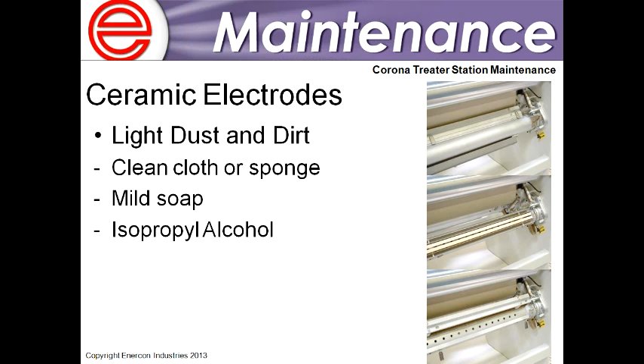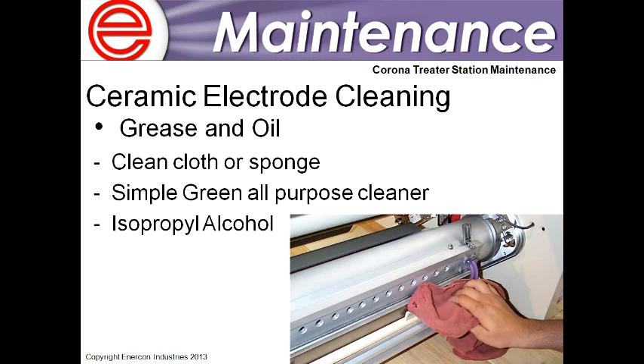You also want to make sure, to Matt's point earlier about surface prep, and I've seen this quite a bit over the years, people will take an alcohol and a cloth and wipe the surface of the electrode down, but they will not remember, or some don't even realize, that the electrode assembly has hinge features that let them access the back of the assembly. So it's really important that when you are taking the time to do this quick maintenance step, you open the electrode assembly and take that same cloth and alcohol and wipe the back of the assembly off, because the mounting tabs and mounting blocks of the electrodes are all accessible now, and you can clean those off. That same dirt and debris that you see on the face of the electrode is likely also deposited on the mounting tab and mounting block, and those parts have to be wiped down as well. Thanks, Tom.